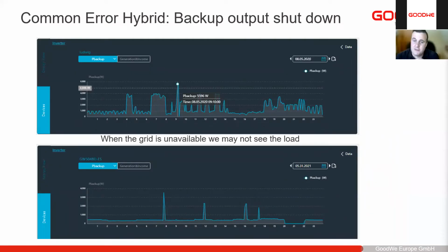So like I said, that curve, here's the example that I was talking about earlier. This device is an ES 4.6. So the ES 4.6 can overload for a certain period of time. On the top, we've got an example. When the grid is available, this device was overloading above 4.6 kilowatt for quite some time before it shut down. So here we can quite clearly see what load caused the device to shut down.